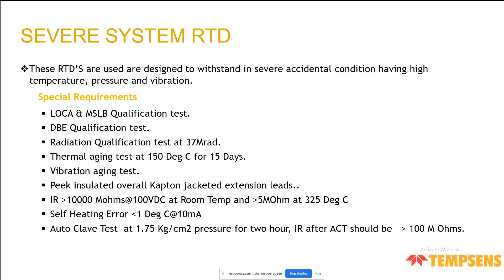Then the same for severe accident systems. After the Fukushima accident, NPCIL has introduced some extra RTDs which are to be put even for the case of a severe accident. So these temperature sensors or instruments should work. They have to be qualified for LOCA, MSLB, and they have to have DBE qualification and radiation qualification. So it is a much more severe requirement than the earlier RTDs. The construction is similar, but the application is much more stringent, so it needs much more care to manufacture these RTDs.